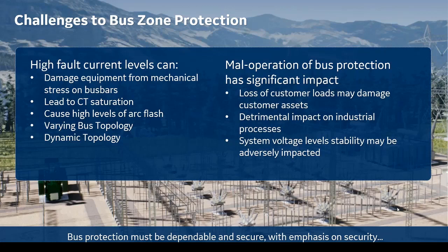And security of bus protection is very important. You do not want to misoperate on a bus because it affects multiple loads, right? If I trip a bus out, I'm going to cause loss of customer load, which could lead to damage to customers' assets and a detrimental impact on industrial processes. I have downtime in multiple processes, and stability issues, because the amount of short circuit current that I'm going to draw for that bus fault can cause stability issues.